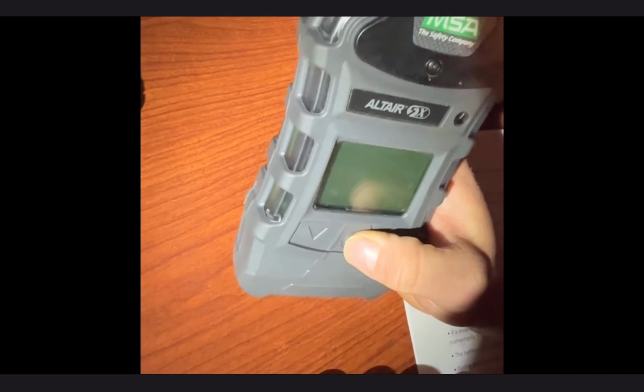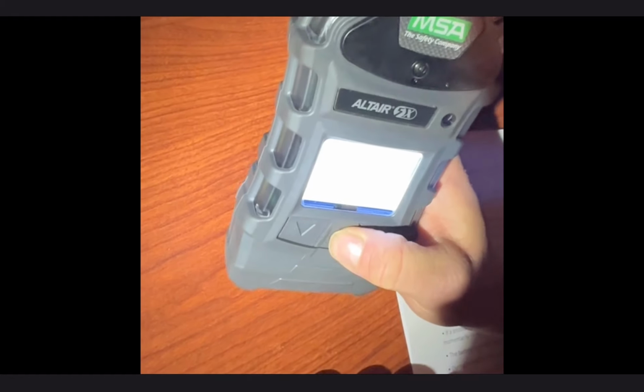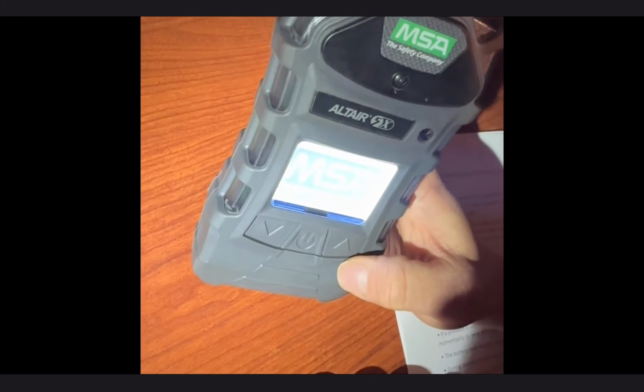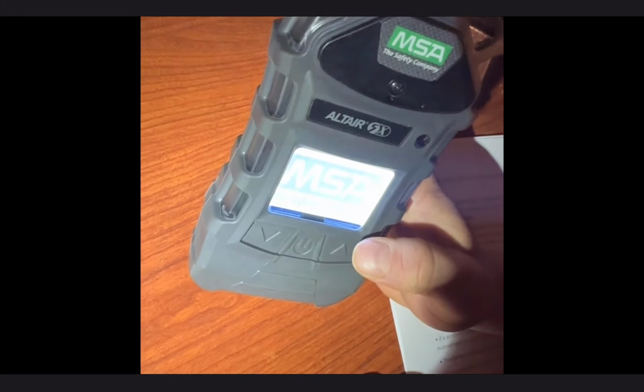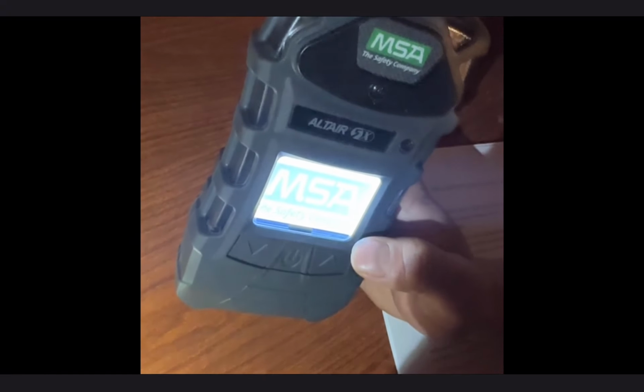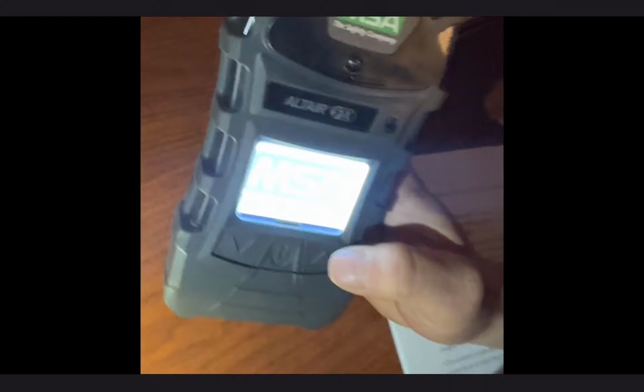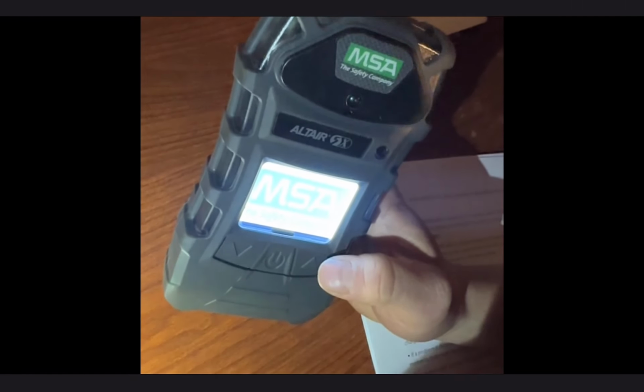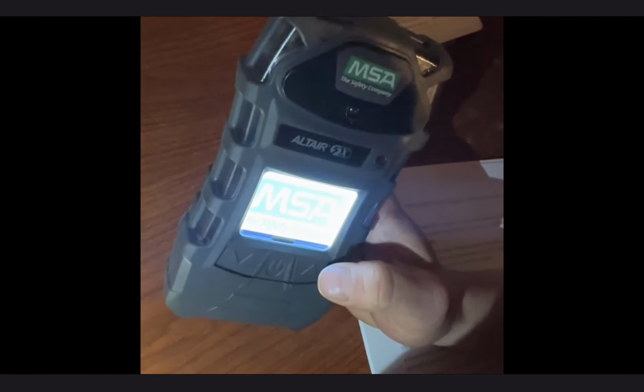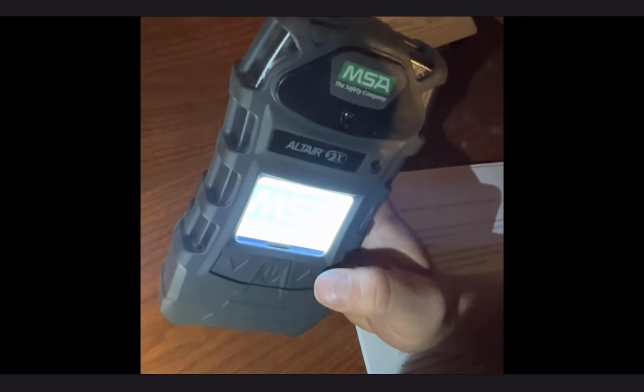So going through here, same startup procedure, just hold the power button on. It's gonna alarm, and it's gonna go through the settings. The reason monitors take a while to warm up is because that LEL is like an electric stovetop grill. So it's heating up that sensor, so at a microscopic level it could do combustions to see what the LEL atmosphere is.